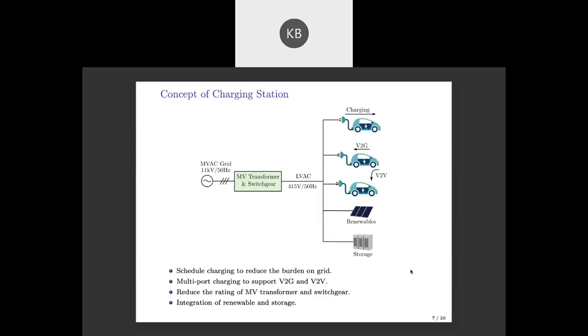So definitely this requires a dedicated charging station. If you suddenly put 3 or 4 cars, each say 200 kilowatts, that's more than half a megawatt of power drawn from your distribution grid. That's a sudden large amount of power, and it can easily destabilize your distribution system.